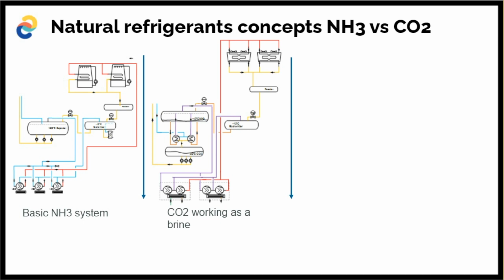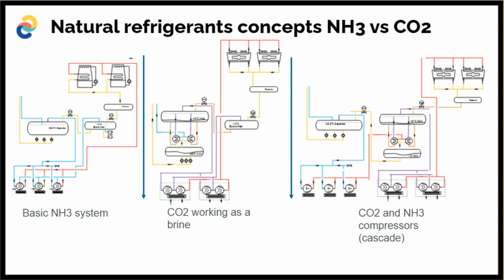And the last one we use a lot is the CO2 and NH3 compressors, a so-called cascade system. They work in cascade, so you have two types of compressors here: CO2 compressors, which are subcritical, not transcritical, and high-stage compressors that actually act as a condenser for the subcritical CO2 side. So these are basic concepts, of course, and for every single distribution center we're going to look at what is the best solution, because every story is different again.